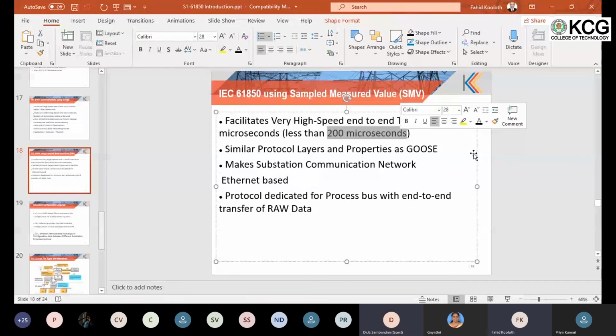Fiber optic fast Ethernet is recommended for this. Even though the standard recommends 200 microseconds for the sample value and 3 to 4 milliseconds for the GOOSE, it is completely dependent upon the utility, what their requirement is, and they can cut it down. For example, in a normal application scenario, the GOOSE can be within 10 milliseconds, and sample value you can have within 500 microseconds if the application scenarios are suitable.